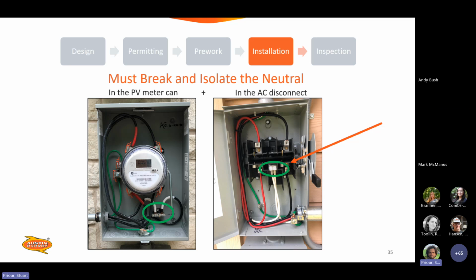So please break and isolate the grounded conductor, the neutral, in both the meter can and the disconnect. You can see here, hopefully, that they've done that by approved means, which is a Polaris block or similar is fine. Also an isolated neutral bar in the meter can. Both of those are acceptable ways to break and isolate the neutral.